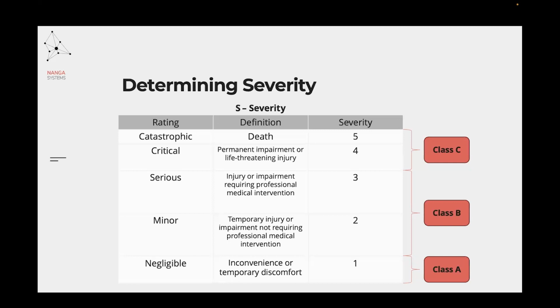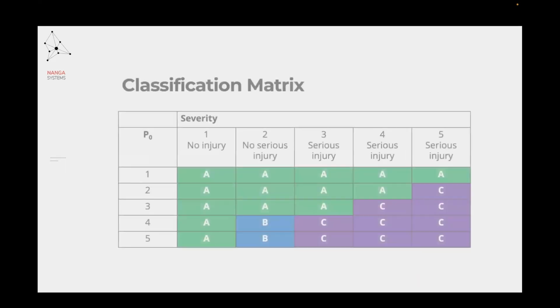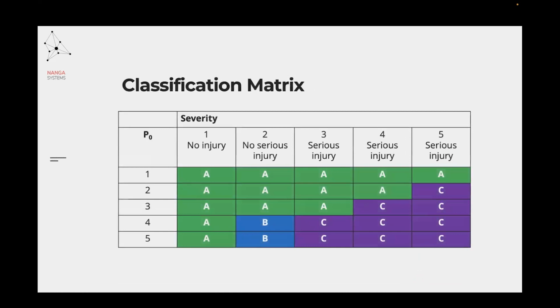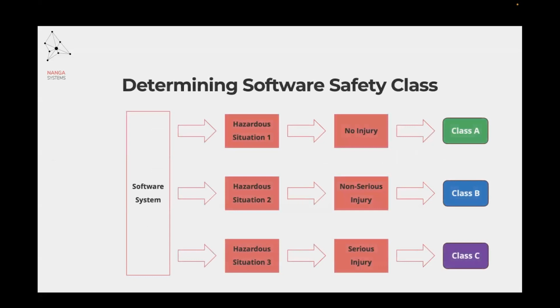Why do we need these values? Because we have a classification matrix which we can use, and using the classification matrix after determining P0 and the severity values, we are going to be able to determine what is the safety class for the software or software item that we are evaluating. It is important to highlight that the same software system might result in different hazardous situations. All these have to be evaluated, as you can see here.